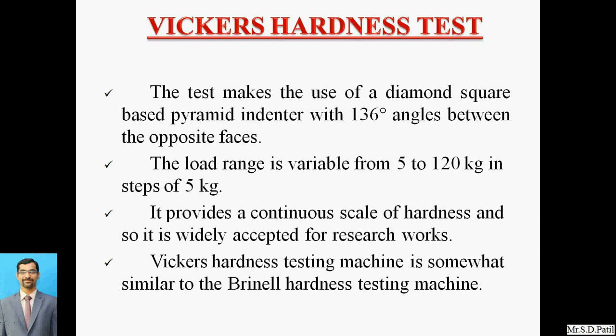Now the Vickers hardness testing machine is somewhat similar to the Brinell hardness testing machine. Nowadays, many Brinell hardness testing machines have the arrangement for the Vickers hardness test, so they can be used for Vickers testing purposes also, to get the Vickers hardness number. Only the indenter has been varied and they have arranged the load carrying capacity. In the Brinell hardness testing machine, I have shown you both arrangements, for the Vickers as well as for the Brinell. The only difference is that for Brinell we are using the ball indenter, with a maximum load carrying capacity of 3000. Here we are using the diamond indenter.